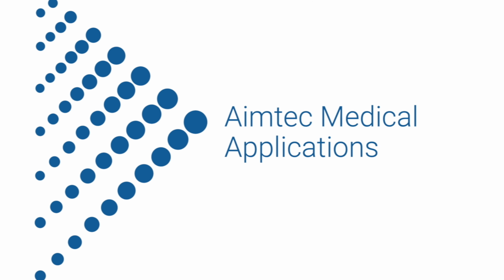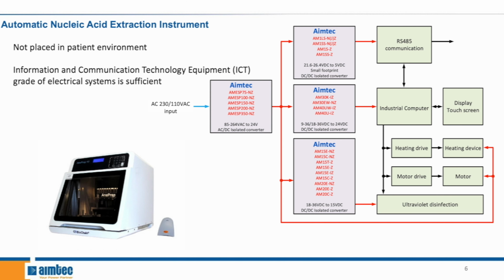Now we'll be moving on to how Aimtec power supplies can be used in various medical applications. First off, we have the automatic nucleic acid extraction instrument. This is the starting point of most biomedical experiments. As a nucleic acid extraction device is not placed in the patient environment, the information and communication technology equipment, or ICT grade, of electrical systems is sufficient. However, high EMC performance and strong interference immunity are needed to prevent interference to the data acquisition device. In the block diagram, we can see a communication module, industrial PC, HMI, and so on and so forth.